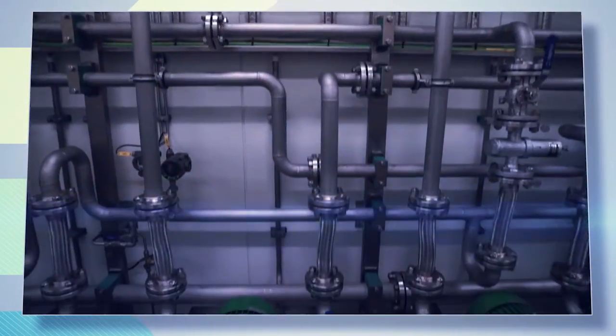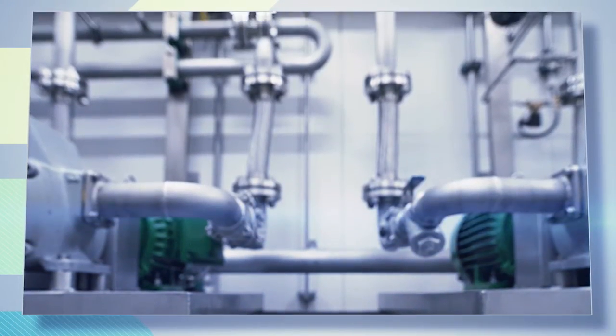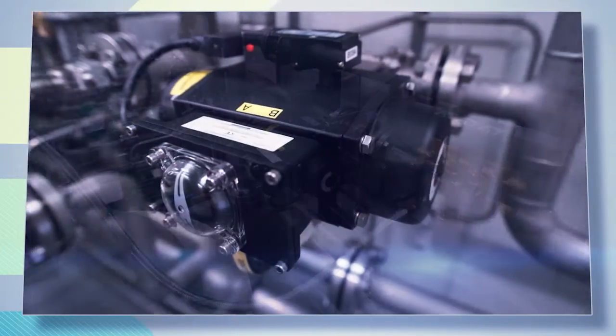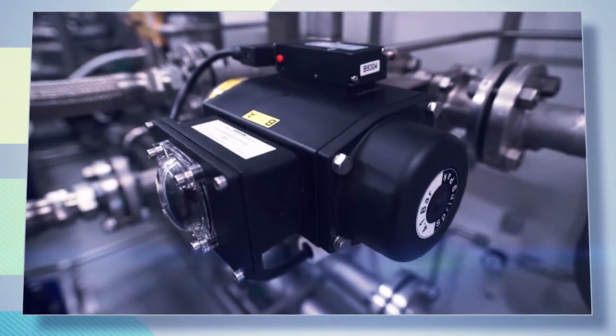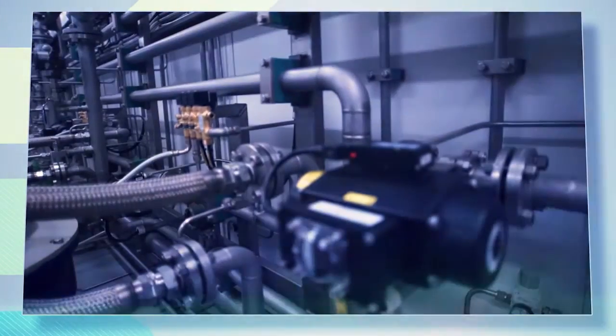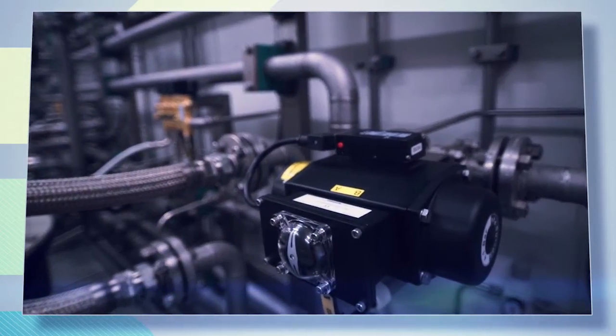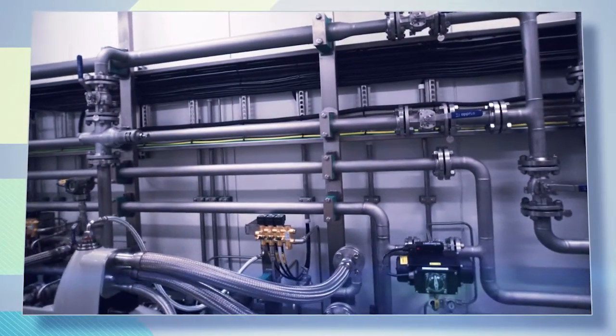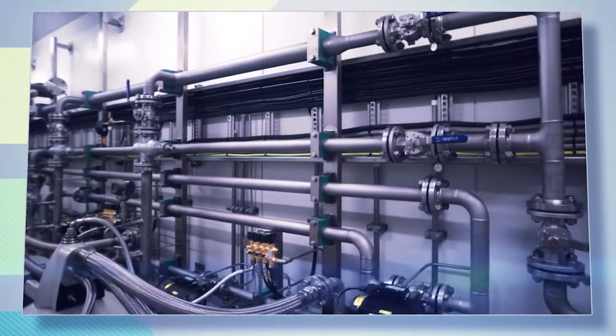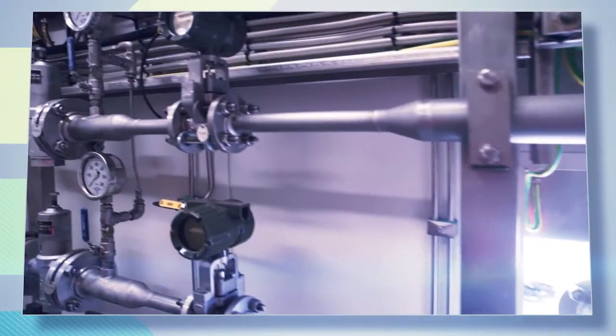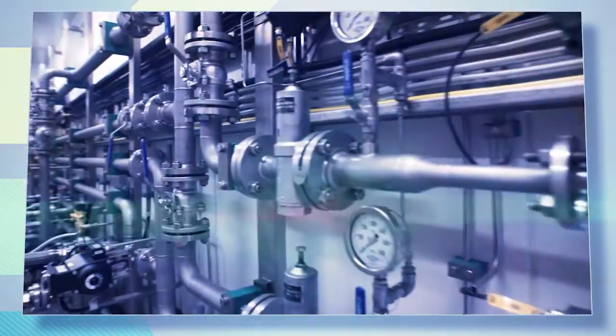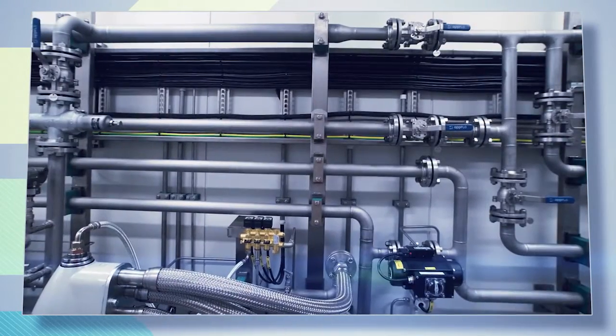The fuel feed pumps draw from the clean tanks, each pump typically servicing a dedicated turbine. Should a fuel feed pump fail during normal operation, the crossover valve will open to maintain fuel supply to the turbines. Fuel feed pump return lines are fitted with pressure control valves and flow meters to ensure constant delivery pressure and flow availability at the turbine connection.